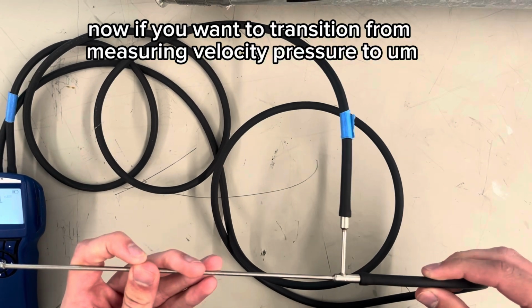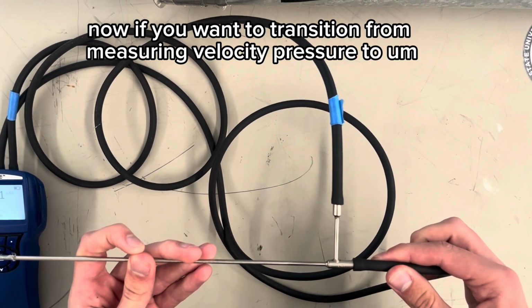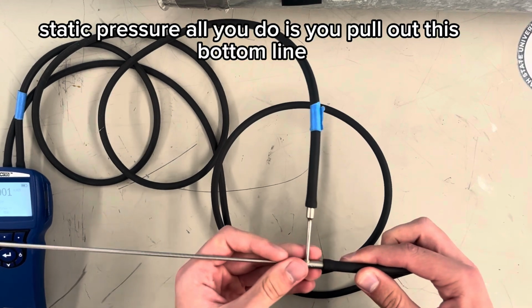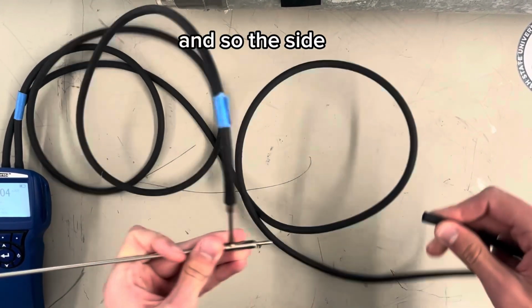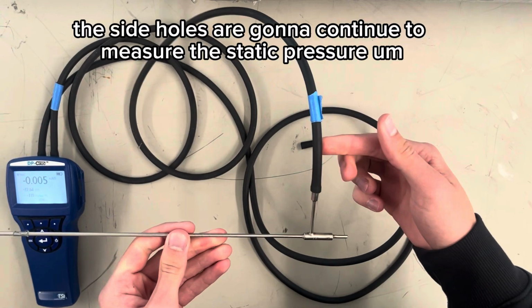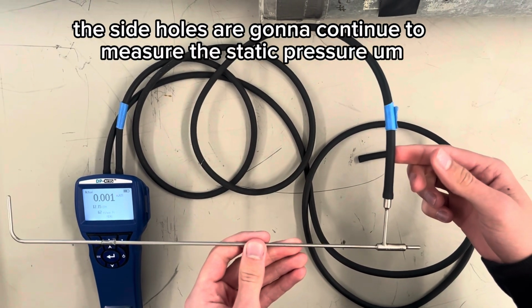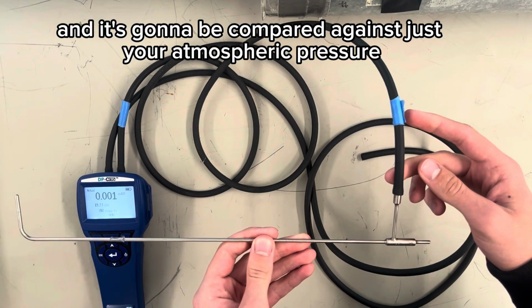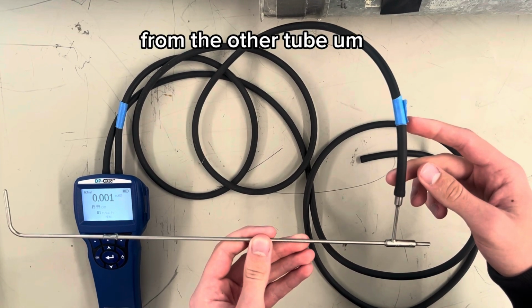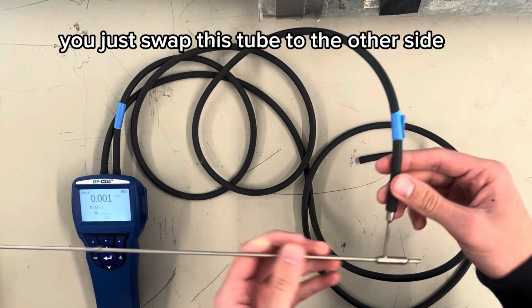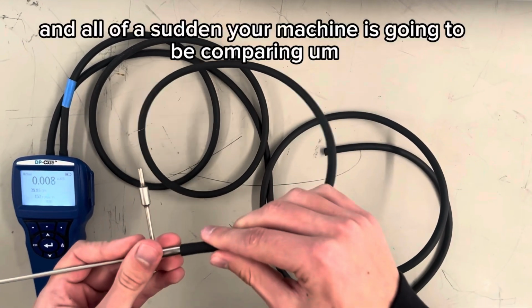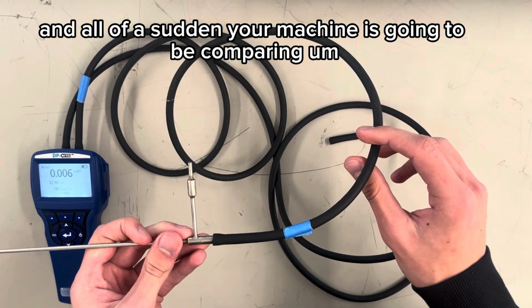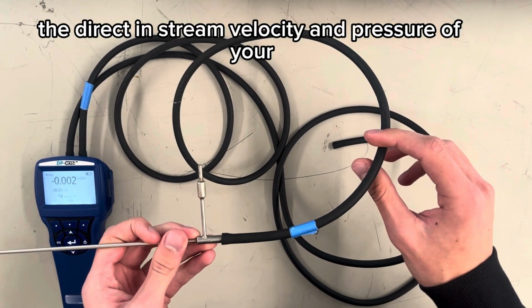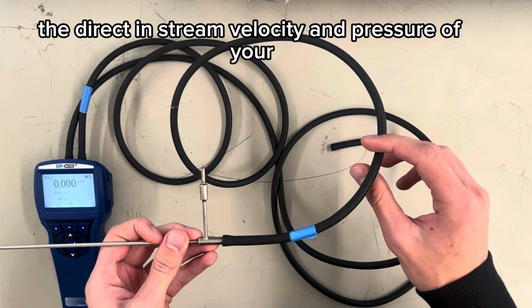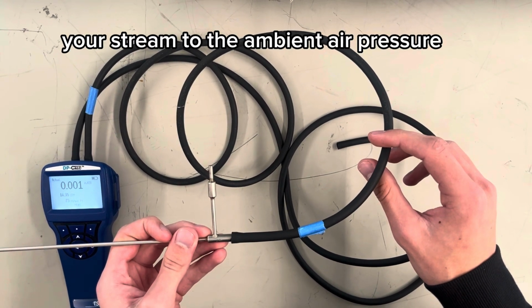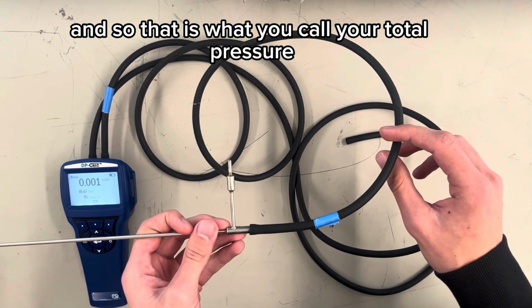Now, if you want to transition from measuring velocity pressure to static pressure, all you do is pull out this bottom line. These side holes are going to continue to measure the static pressure, and it's going to be compared against just your atmospheric pressure from the other tube. If you want to measure total pressure, however, you just swap this tube to the other side, and all of a sudden your machine is going to be comparing the direct in-stream velocity and pressure of your stream to the ambient air pressure. And that is what you call your total pressure.